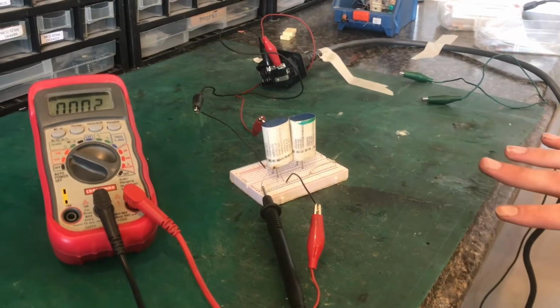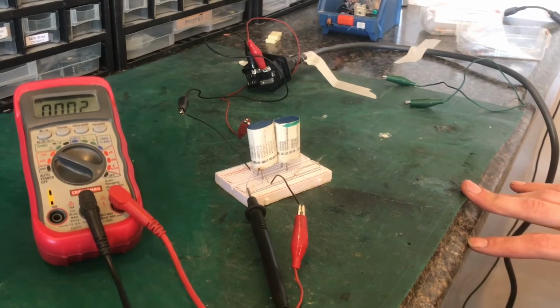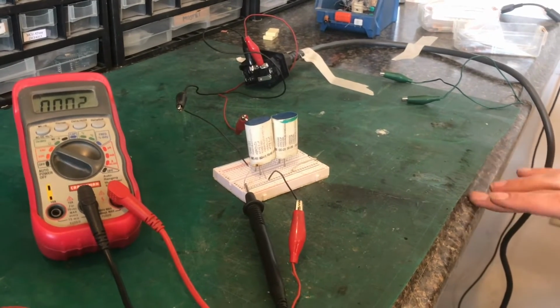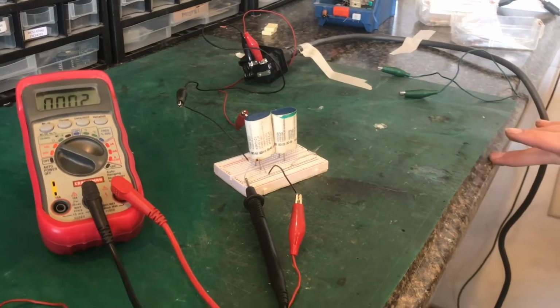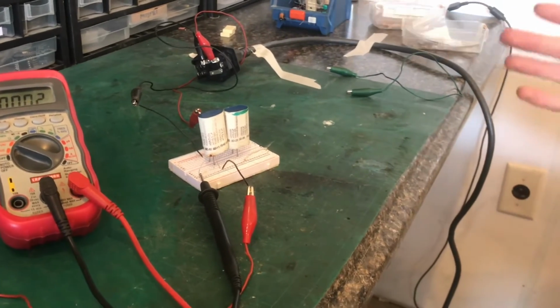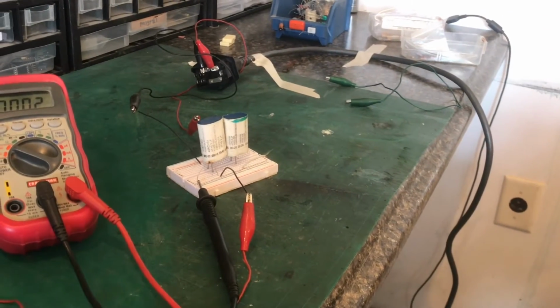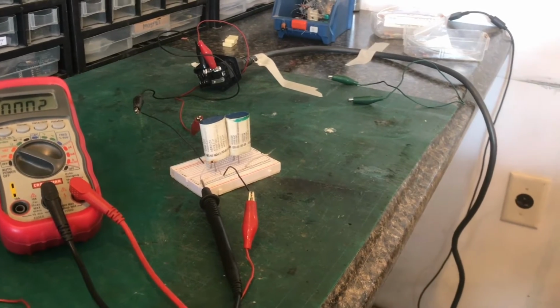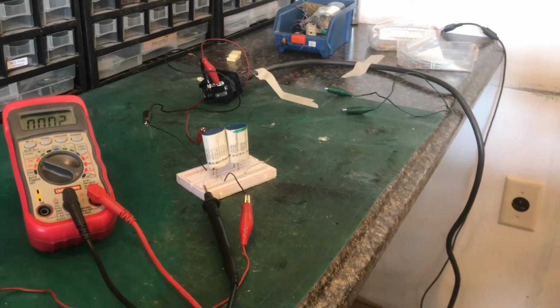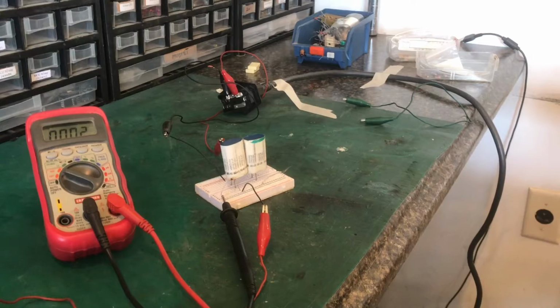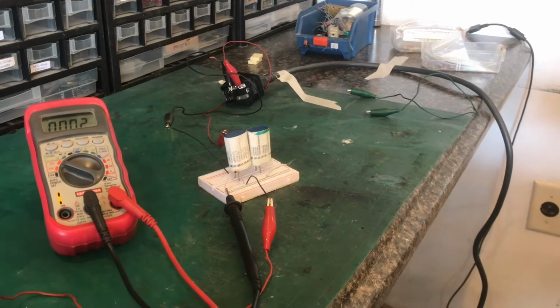Basically, that's so that as a person I can touch earth ground, or just be standing on the ground and touch live on the secondary side of the isolation transformer, and I won't get hurt, because the secondary voltage is not referenced to earth ground.